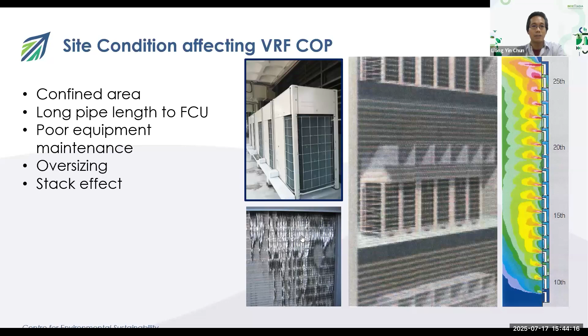Because of all these reasons, the VRF may not perform as stated in the catalog. The catalog values from Daikin and Mitsubishi are actually obtained from a factory tested, controlled environment. But once you install the VRF system on site, all these problems I mentioned can affect the VRF COP value, the efficiency value.